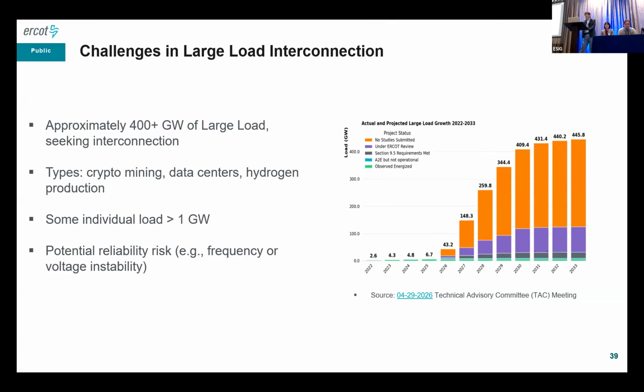They're not traditional industrial load. As mentioned by Eric this morning, close to 90% of them are data centers or crypto mining load. Their size is not small. Some of the individual loads are huge, 1 gigawatt or 2 gigawatts. And they are packed with power electronics components, similar to IBR. They are very sensitive to some system disturbances, particularly in weak grid conditions. So we have a lot of concern. Imagine tens of gigawatts of large load data centers sitting in the weak grid region and tripping all at the same time without riding through the fault. It can be a huge challenge for our system operations to manage.